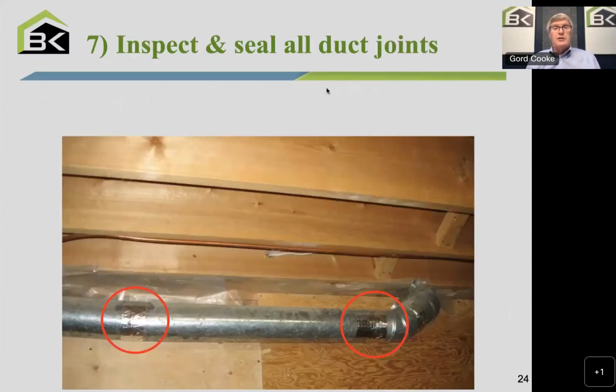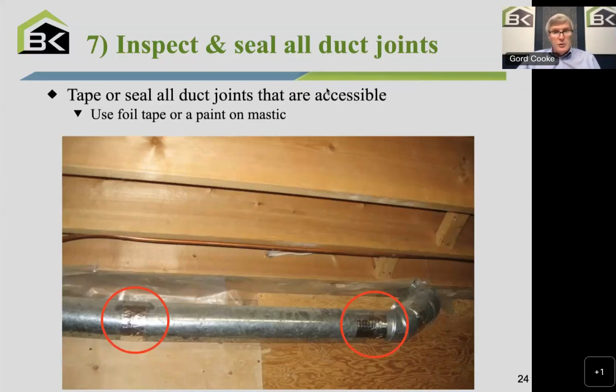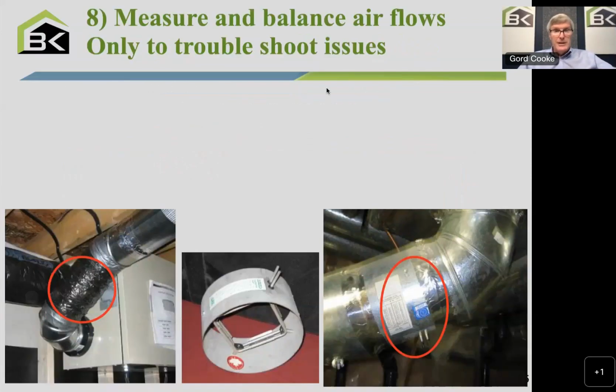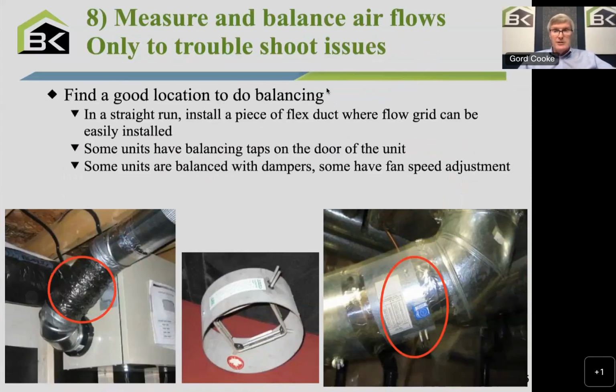And then it is a good time to inspect and make sure all the other duct joints, the ones coming from the bathrooms and so on, are sealed correctly. So we want to keep that in mind. We tape or seal those joints if they haven't been already, using that foil duct tape. And in some cases, if there have been issues, they're not getting proper airflow, you check the outside hoods, there's no airflow, or the unit's freezing up all the time, it may be imbalanced. You remember we said we want the same amount of air coming in as going out. Well, there's a way to measure that.